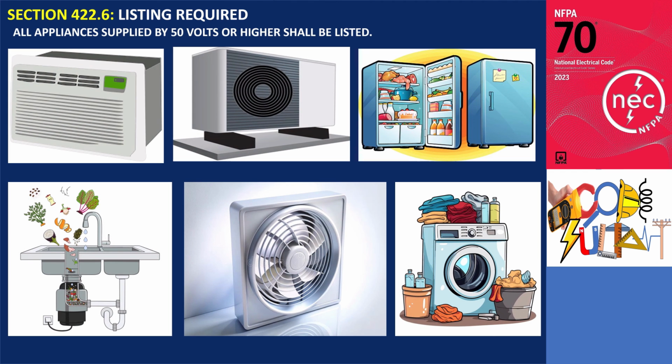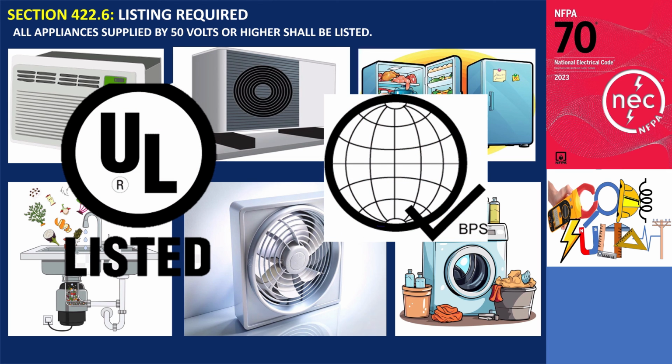Section 422.6, Listing requirements. The National Electrical Code mandates that all electrical appliances operating at 50 volts or higher must be listed by a qualified testing laboratory. This ensures that appliances have met specific safety standards and have been tested for proper operation.